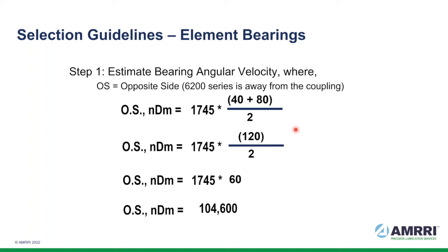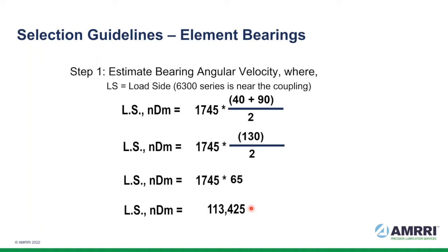Plugging the numbers from the bearings we were just looking at into the equation, 40 millimeters plus 80 millimeters divided by 2, 120 millimeters divided by 2, 60 millimeters times shaft speed gives us the NDM value. This is an attribute from the bearing itself. That was for the bearing furthest from the coupling. The bearing closer to the coupling is slightly larger.